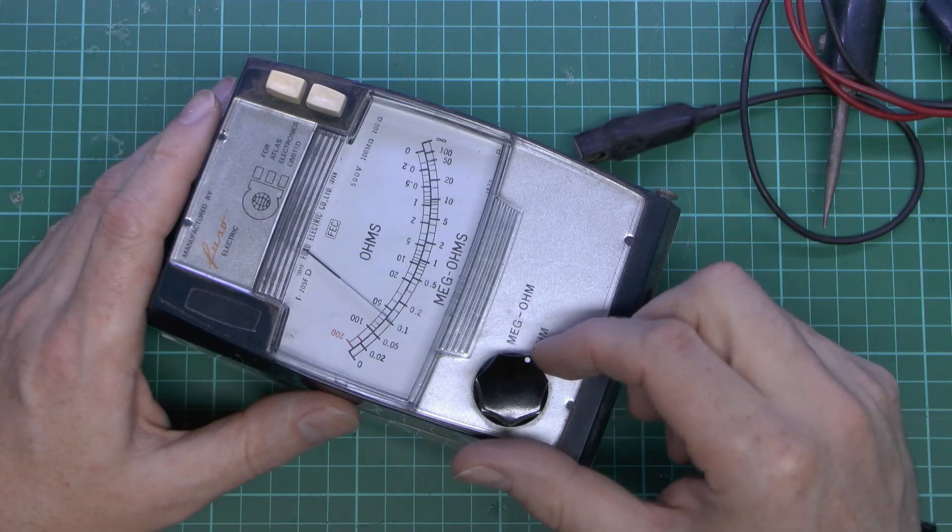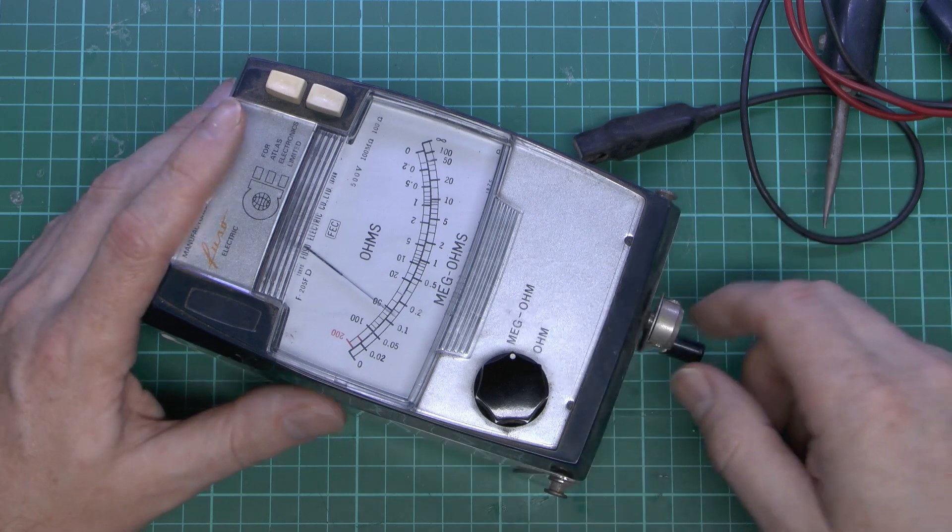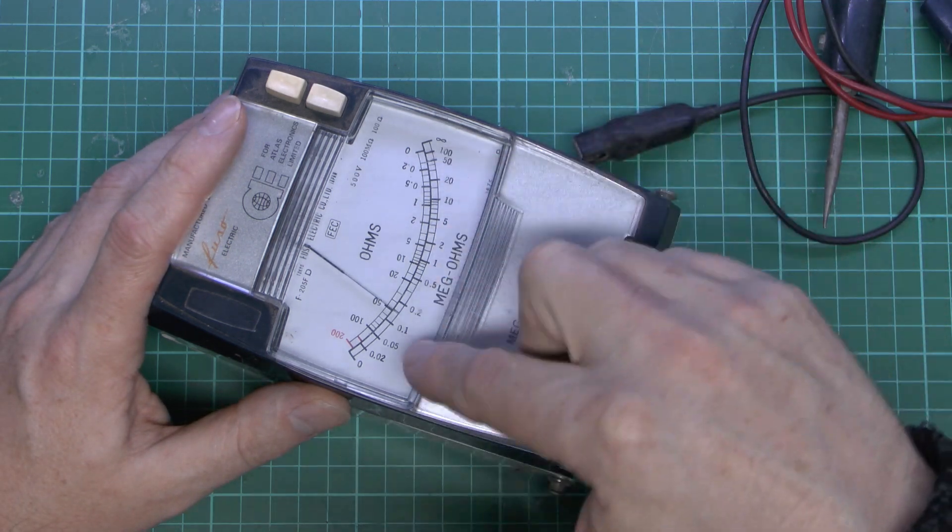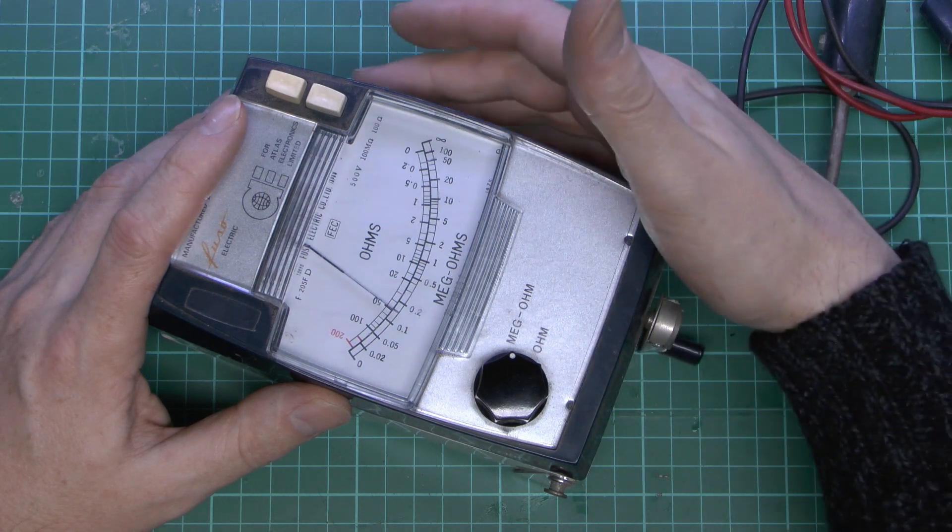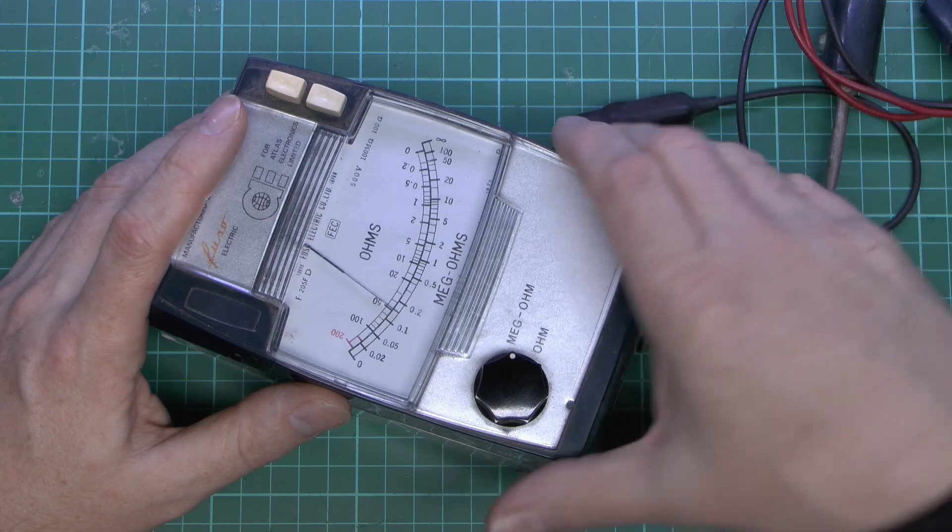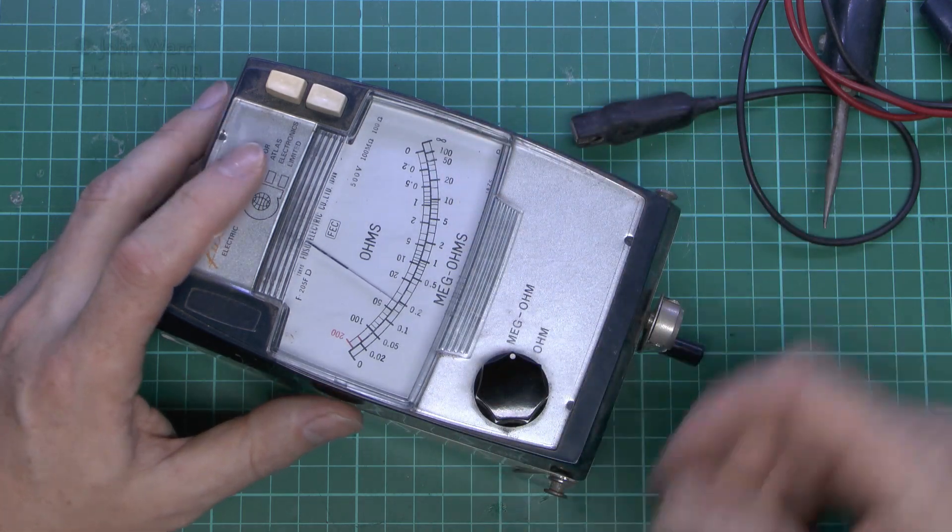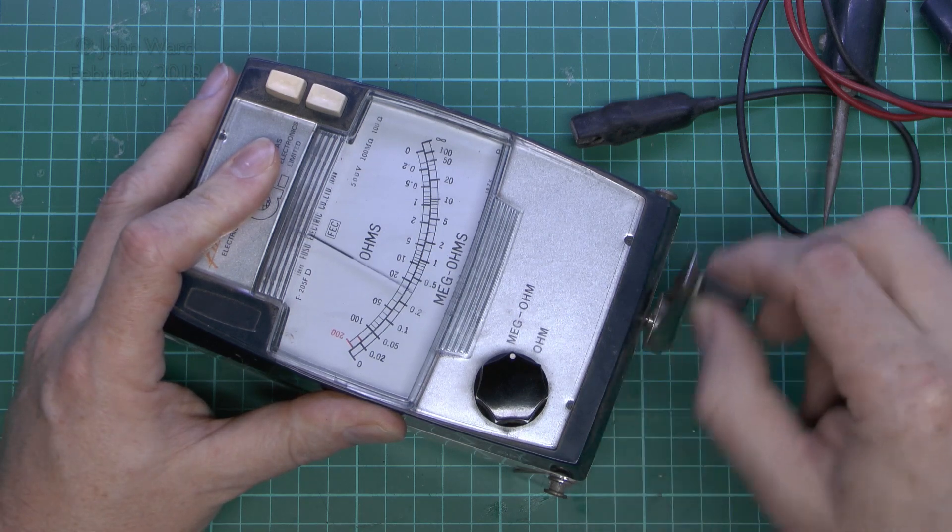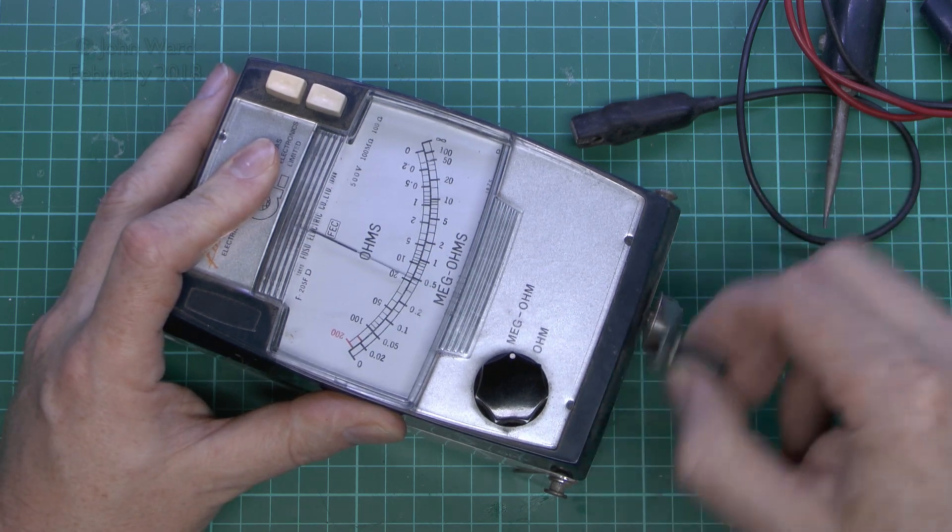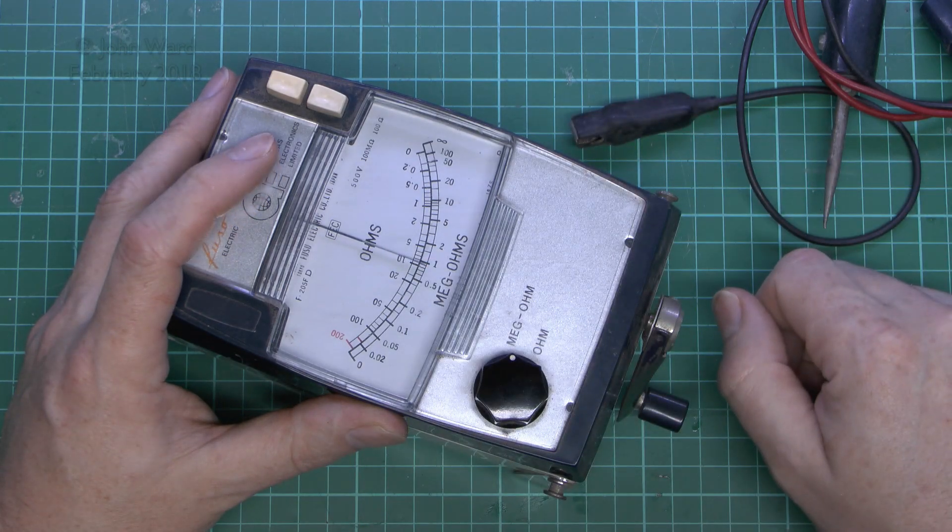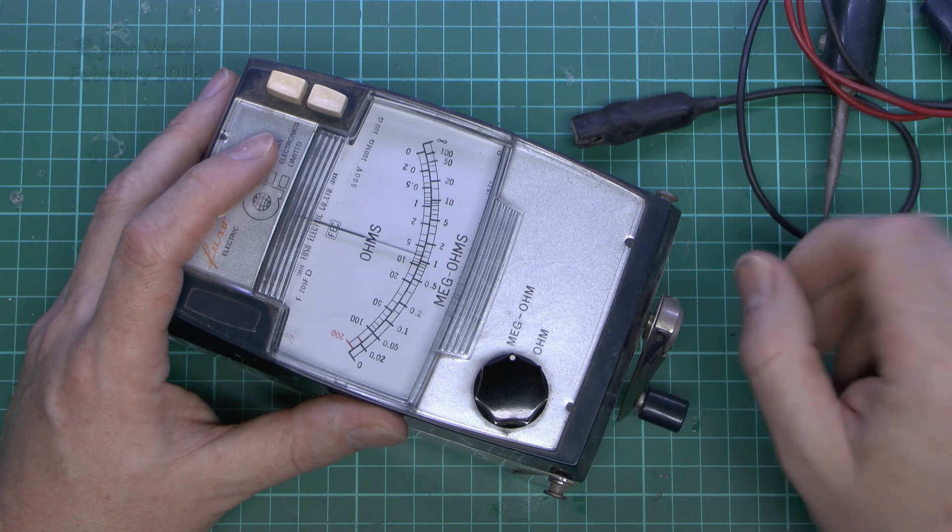Now the way it's supposed to work is that on the megaohms scale here, turning the handle would generate about 500 volts, and then it would show the appropriate resistance here. Now with nothing connected, it should go up to the infinity end there, because basically there's no thing attached at all. So basically as high as possible, but if we set it there and actually turn the handle, as you can see it doesn't. It basically sort of creeps along somewhere in the middle, so definitely something wrong there.